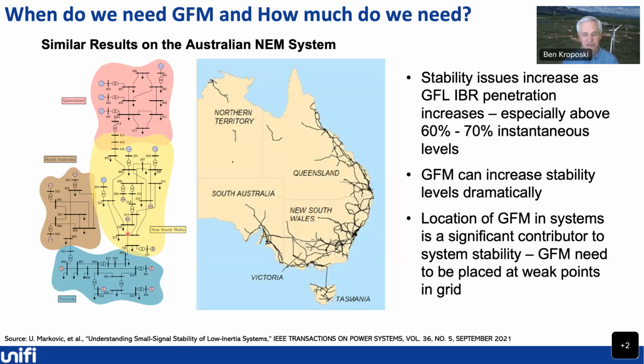In general, the 60 to 70% is a level, and again, that's instantaneously, which we're going to be reaching very quickly. You can get to those levels even with 30% renewable deployments on an annual basis. And how you actually deploy these in your system, making sure to strengthen the weak places in your grids with grid forming inverters, will be critical moving forward.